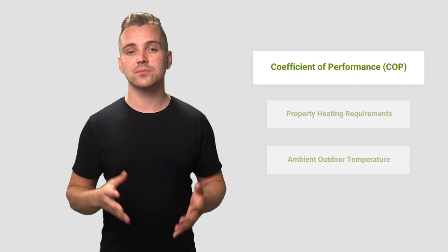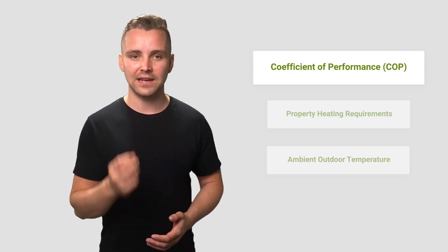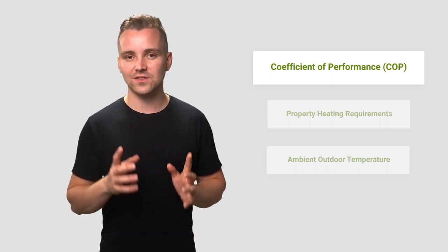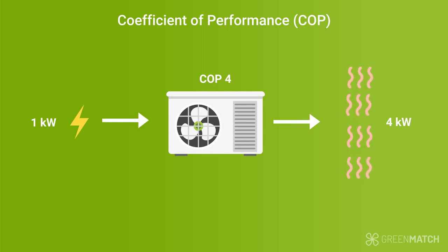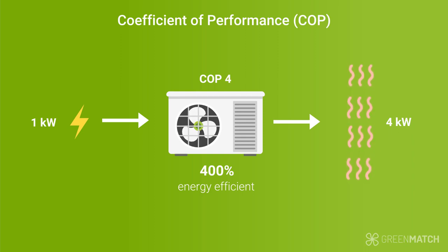An air source heat pump's coefficient of performance is a number that defines how many units of heat in kilowatts it can produce from a single kilowatt of electricity. For example, a heat pump with a COP of 4 will produce 4 kilowatts of heat for every 1 kilowatt of electricity it receives, making it 400% energy efficient. The higher a heat pump's coefficient of performance, the more efficient it will be.